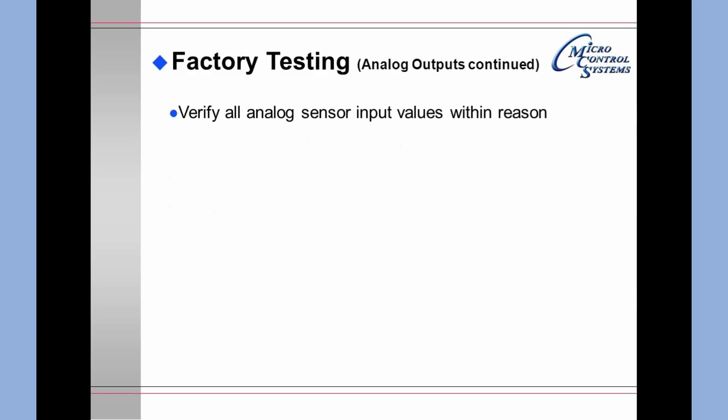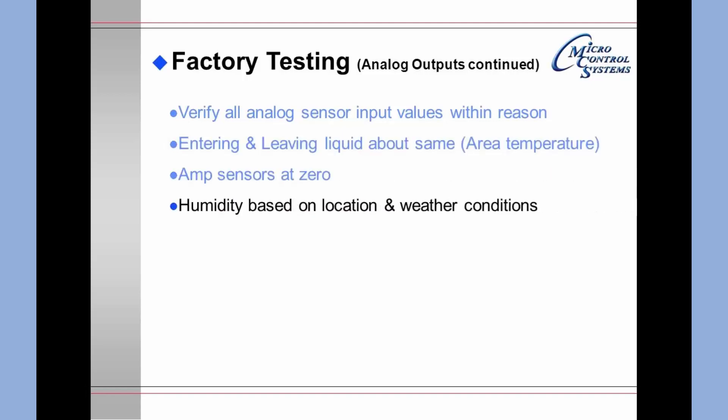Verify that all analog sensor input values are within reason. The entering and leaving liquid should be about the same temperature, and if the system has been off for three or four days, it should match the area temperature. Amp sensors should read zero. Humidity should be based on the location and the current weather conditions.